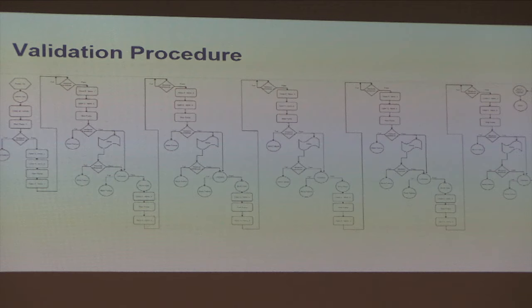This is our much more comprehensive validation procedure, which is used to make sure that the entire system is functioning. Basically, as I mentioned before, it just goes through, gates off every section, pulls vacuum on them individually, holds it, makes sure they're not leaking, and then moves on to the next one. At the end of the procedure, it resets everything so it's ready for the actual operational tests, stores the passes and failures, alerts the user, and continues on to the menu.